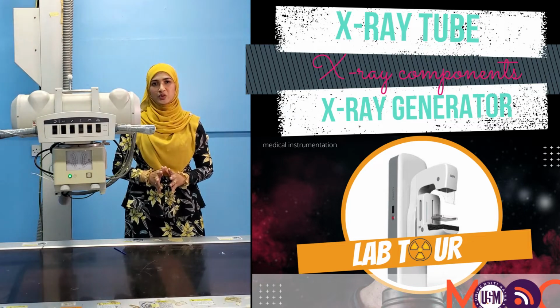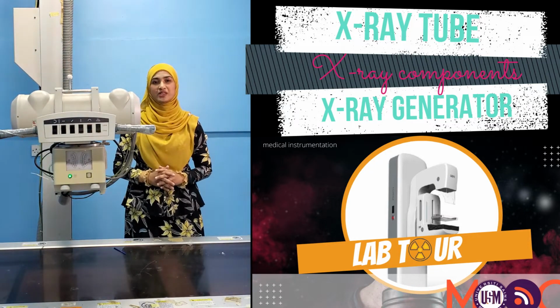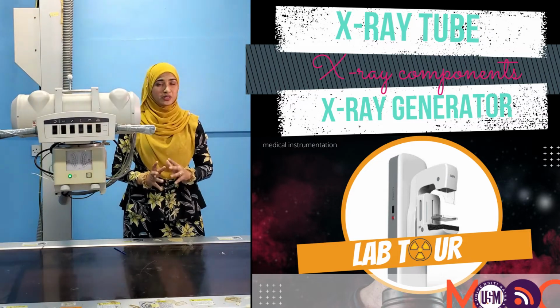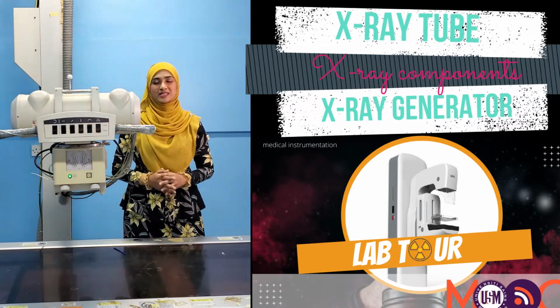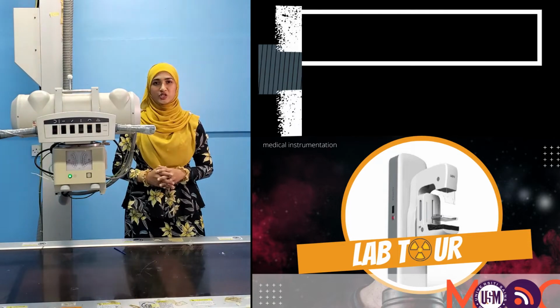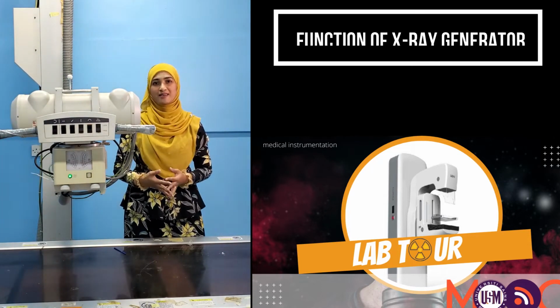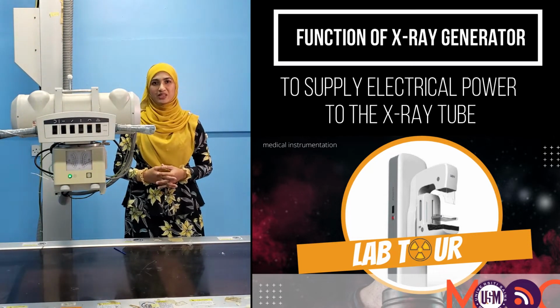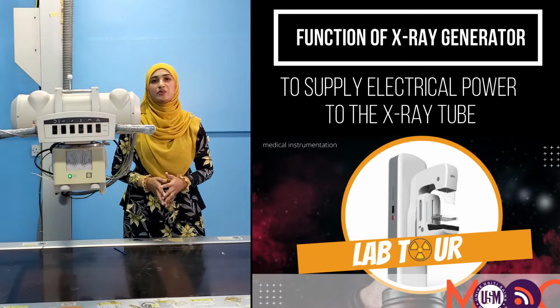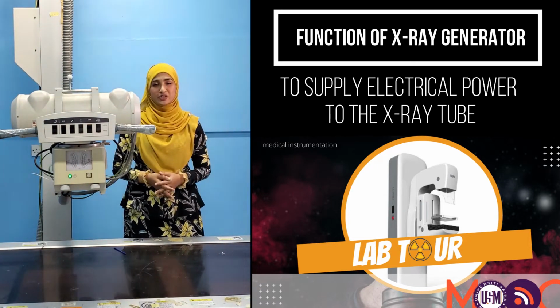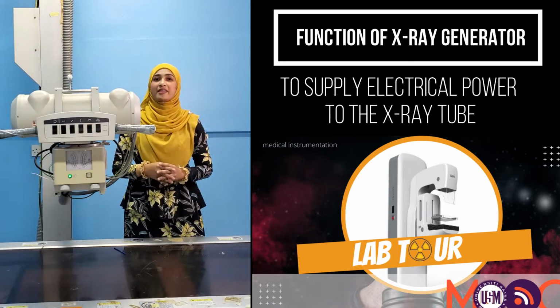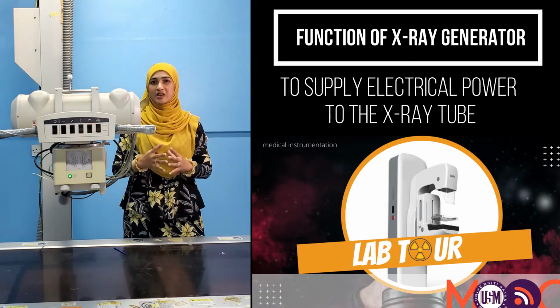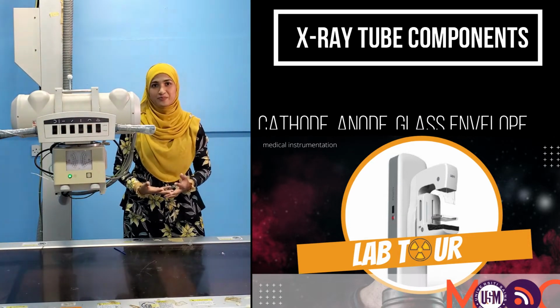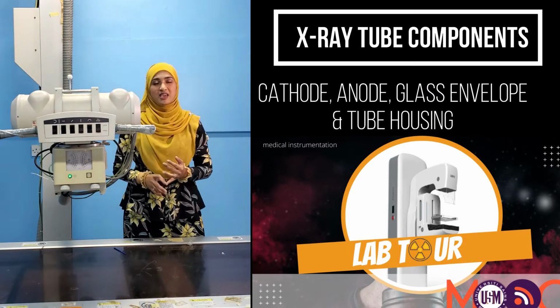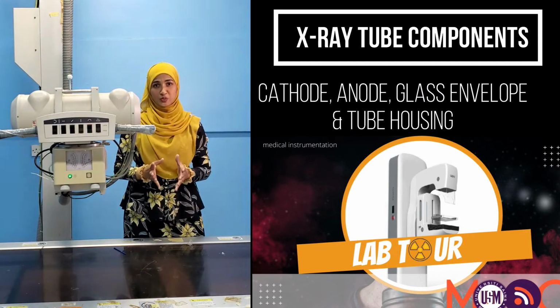But in this video, I'm going to touch only on the details of the X-ray tube, although we are going to touch a bit on the function of the two systems. The X-ray generator is used to provide the input energy to the X-ray tube so that the X-ray tube will produce the X-ray from that energy. From the X-ray tube itself, there are several components that are related to each other in producing the X-ray efficiently, which are the cathode, anode, glass envelope, and also the tube housing.